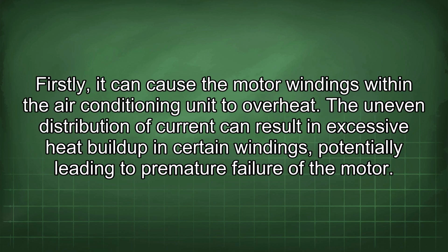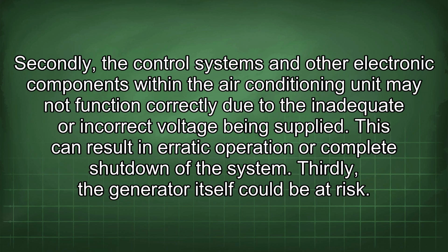Firstly, it can cause the motor windings within the air conditioning unit to overheat. The uneven distribution of current can result in excessive heat buildup in certain windings, potentially leading to premature failure of the motor. Secondly, the control systems and other electronic components within the air conditioning unit may not function correctly due to the inadequate or incorrect voltage being supplied. This can result in erratic operation or complete shutdown of the system.